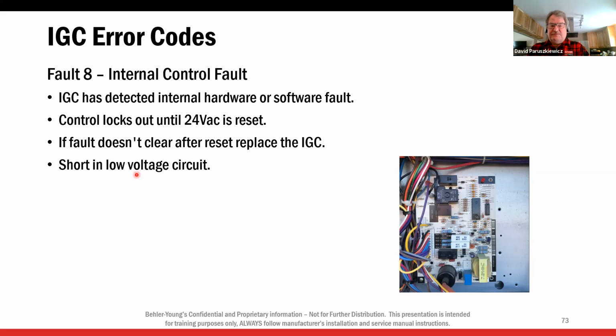You get the common reversed between the high and low stages of the valve. So you've got a short, and we're going to have an 8 fault because it sees the short. So this is typically a short on the low voltage side. The gas valve is bad, or the gas valve is miswired. Those are the most common times I run into this. The easiest thing to do is start unplugging your loads from this, your gas valve, your pressure switch, and see if it goes away. But most likely it's a miswired gas valve or a bad gas valve. You've got a shorted coil in the gas valve.